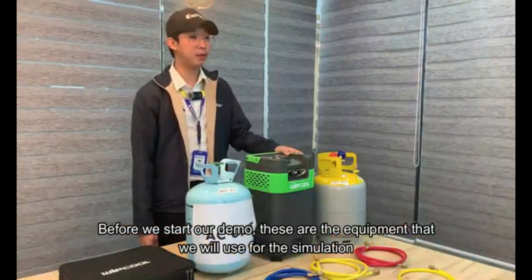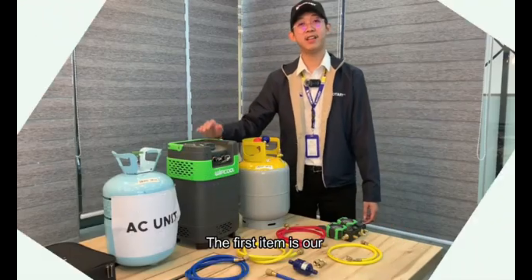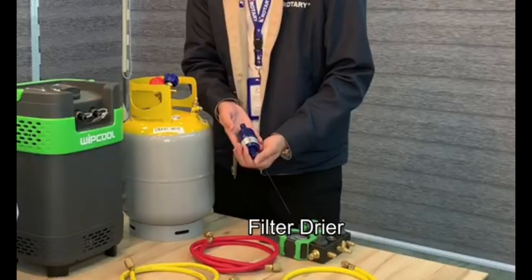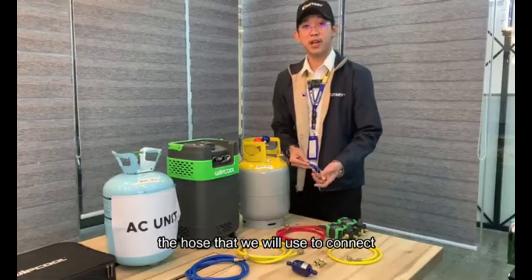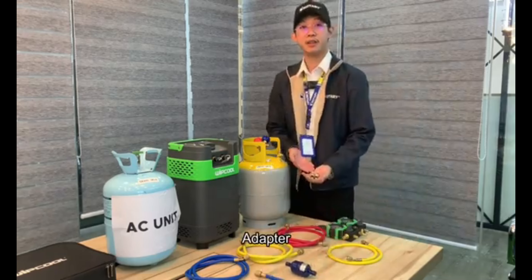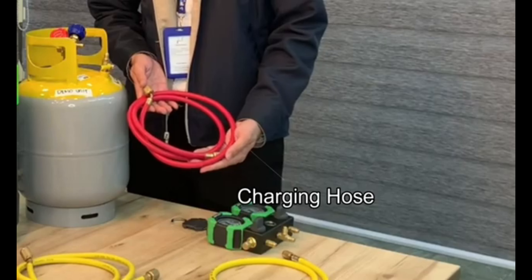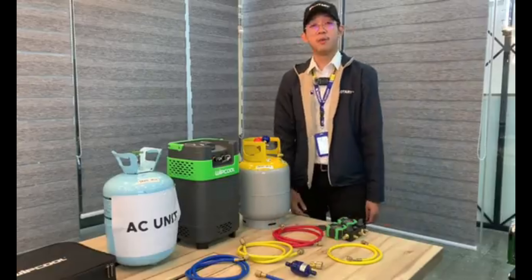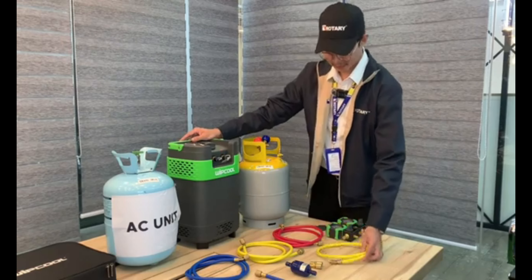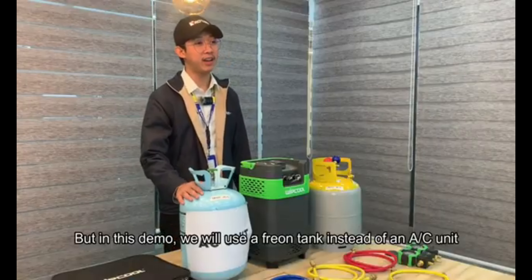Before we start our demo, this is the equipment we will use for this simulation. The first item is our Wipcool Recovery Machine. This item includes our filter dryer, the hose that we will use to connect the filter dryer to our recovery machine, an adapter, and three charging hoses. We will also use an extra charging hose to connect our recovery tank to our recovery machine, and we will use a manifold gauge. In this demo, we will use a freon tank instead of an AC unit.